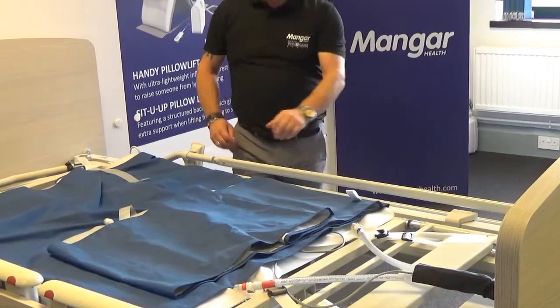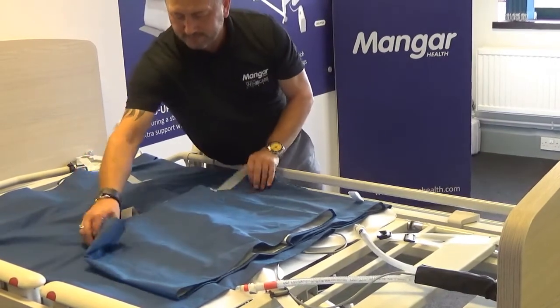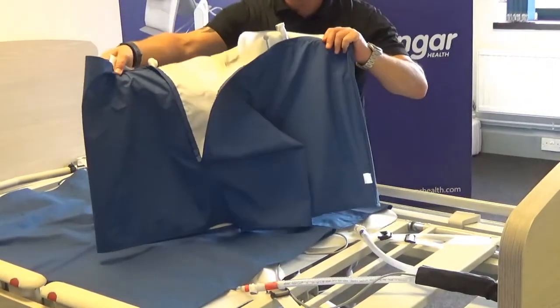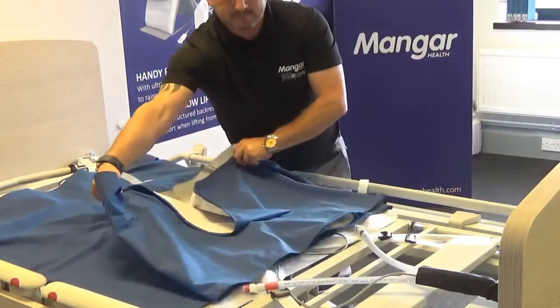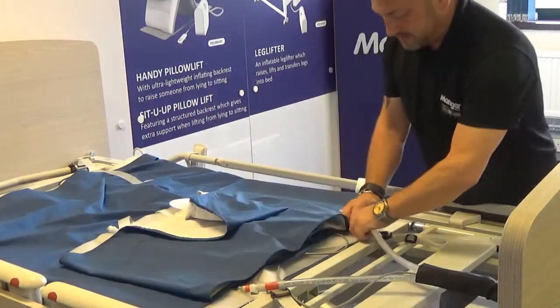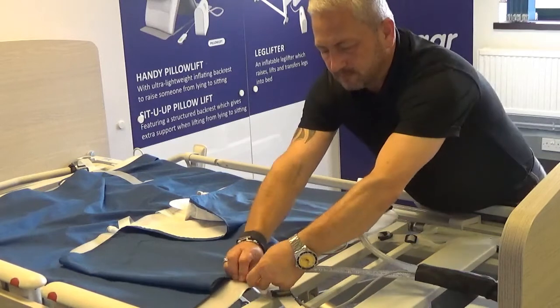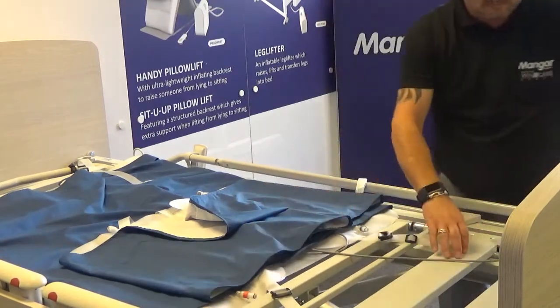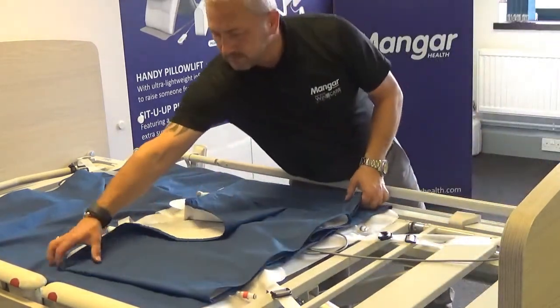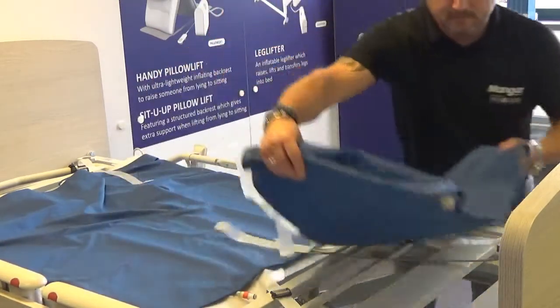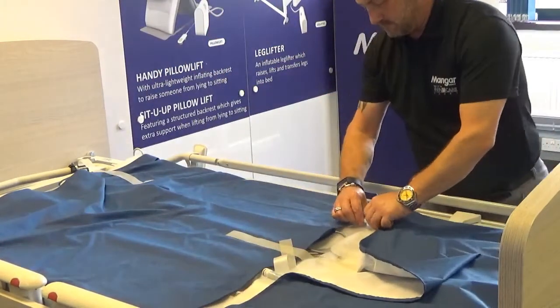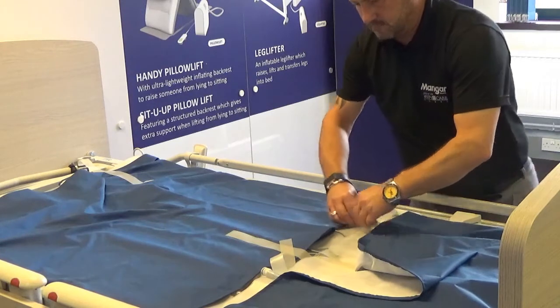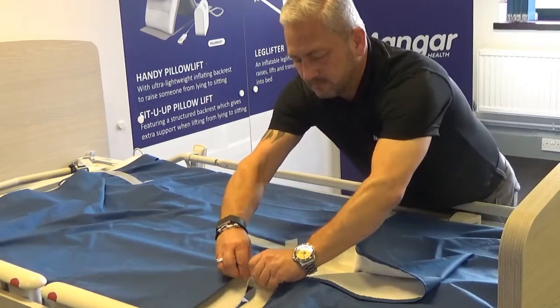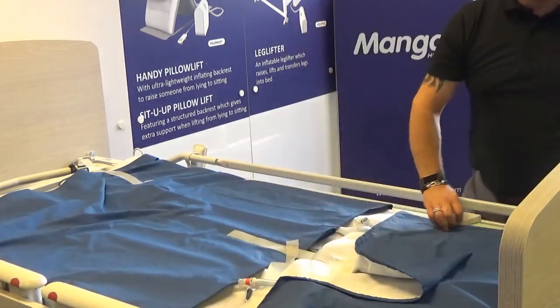For some patients, clinicians may prefer to use the leg extension with the standard Ekamove air chamber system. To add the leg extension, firstly disconnect the air tubes from the air chamber system. Use the connectors on the top end of the leg extension kit to attach to the air chamber system and then reconnect the air tubes to the bottom of the leg extension kit. Always ensure the left and right air tubes are connected correctly.